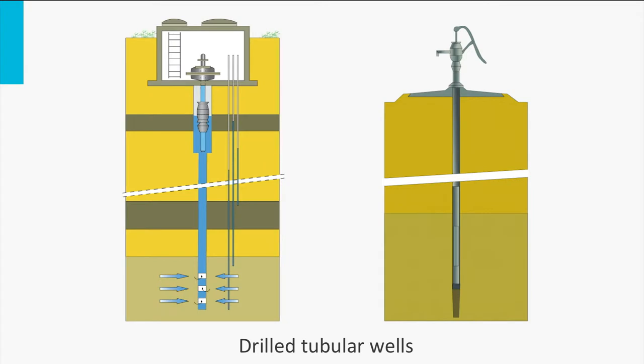The most widespread method for vertical abstraction of groundwater is drilled tubular wells. Considering the required contact area with the aquifer, these types of wells can only be applied in cases where aquifers have enough thickness. A series of wells has to be constructed for larger capacities. Every well can be supplied with its own pump, or it can be centrally drained with a vacuum system.